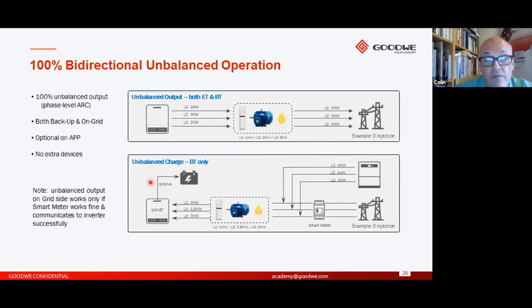If we didn't have the unbalanced charge capability, we'd get a reduced charge amount to the battery. So here we're saying we've got 100% unbalanced output capability, meaning if there was no demand on phase 1 but there was a 3.3 kilowatt demand on phase 3, we can support that.